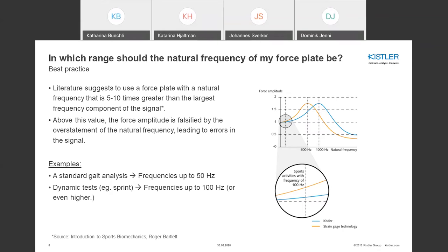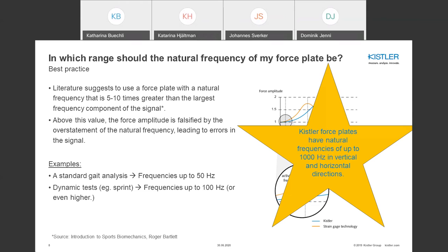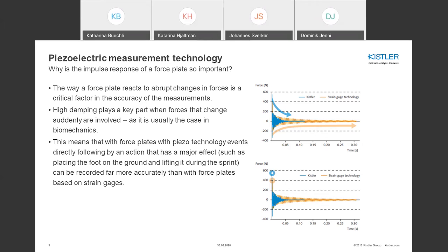It's recommended to use a force plate with a natural frequency five to ten times greater than the largest frequency component of the signal. For gait analysis with frequencies up to 50 Hz, or more dynamic tests such as sprinting with frequencies up to 100 Hz, force plates with a natural frequency of up to 1000 Hz in all directions — vertical and horizontal — can cover nearly all biomechanical applications.